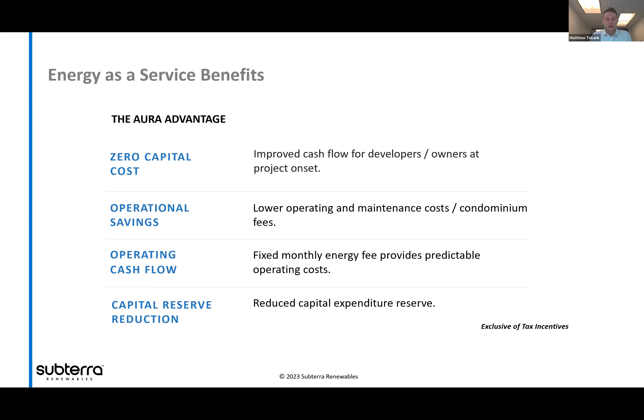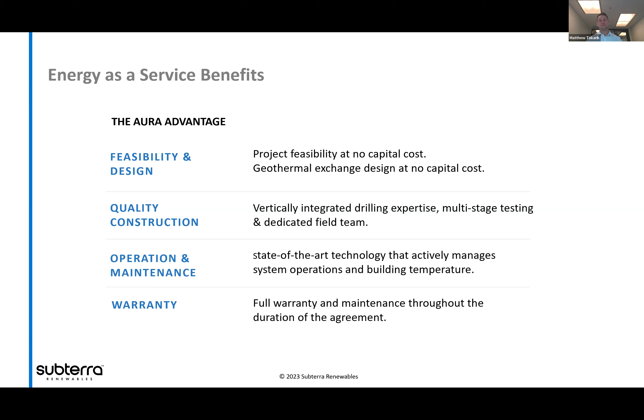In terms of actually putting this together, we bring all the pieces to the table: the design, the construction, the actual drilling. We've got a vertically integrated group that has drillers in-house. We're the ones taking the risk of owning and operating the system, so we do all the repairs, the maintenance, the monitoring, and we've got a performance guarantee that says this is going to work and you're going to get the capacity it was designed for. If not, we're the ones who need to go make the repairs or replace the system to make sure it's operating correctly.